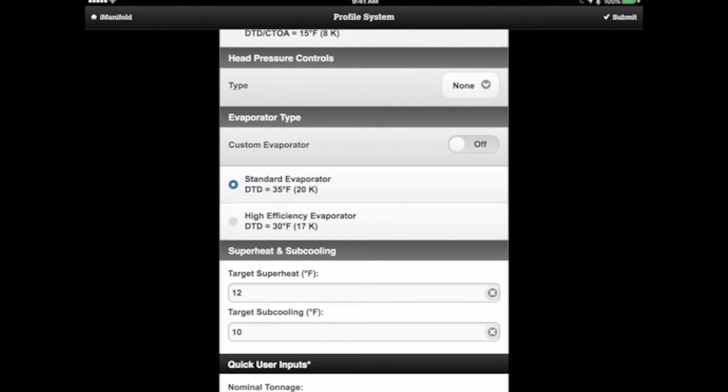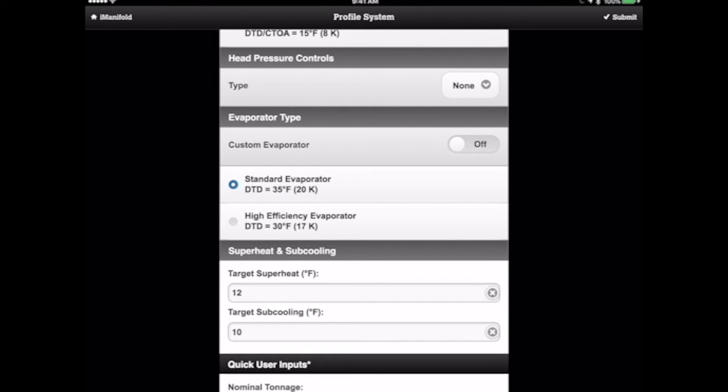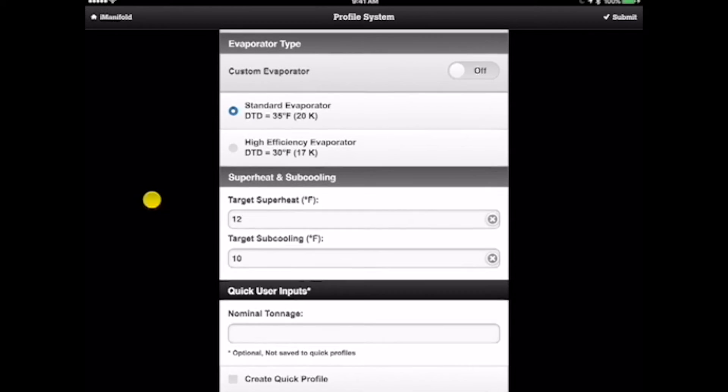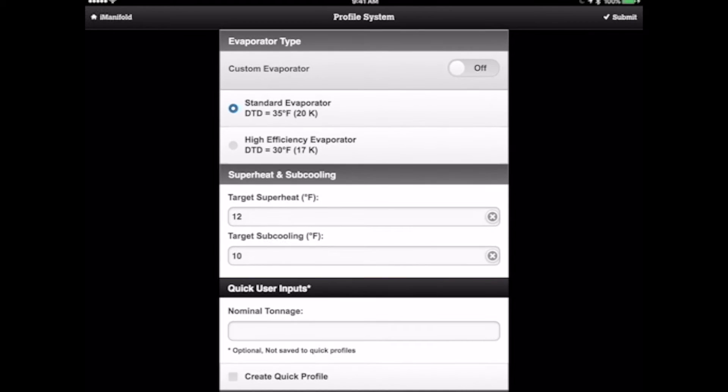These two things you're seeing here, this DTD is design temperature difference. And this can either be 35 degrees colder than return air or 30 degrees. In this case, like I said before, it's a standard evaporator. So we'll go ahead and select that.